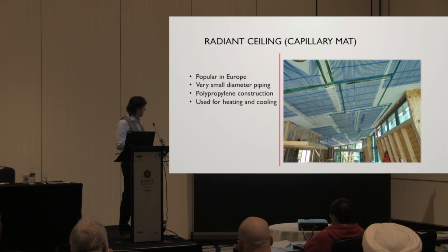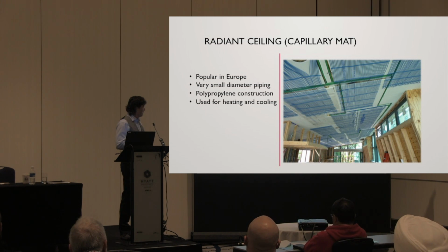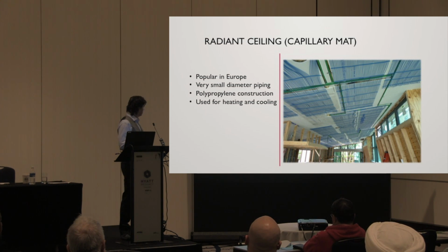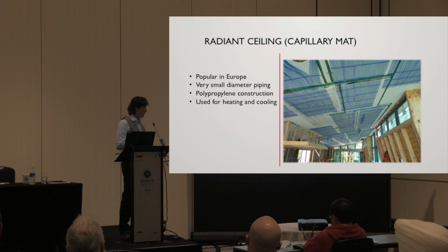This is a German product, and it's called capillary mat. It's quite interesting. The Olympic Village, for example, chock full of this. In Europe, what they do is plaster this in the ceiling. So these are very fine tubes. Super fine. They're like 1/8-inch diameter tubing. You can use them for heating and for cooling. Made out of polypropylene. They're quite popular in Europe, believe it or not.